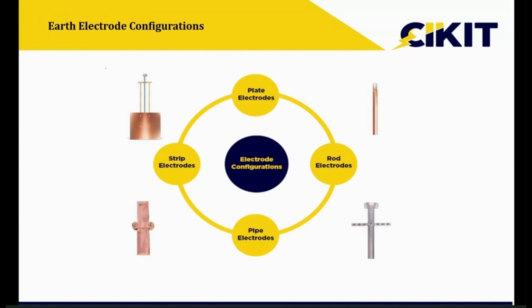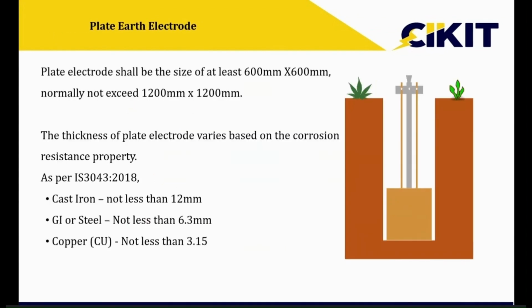The standard has highlighted four different types of earth electrodes: plate, rod, pipe, and strips. If you take the plate earth electrode, generally we use 600 by 600, and depending upon the material, the thickness will be different. The reason for different thickness is to compensate for the effect of corrosion. The corrosion rate is much lower for copper. That is the reason we use only 3 mm thick plates. Whereas if I go for GI or steel, the thickness has to be 6.3 mm, and if it is cast iron, the thickness has to be 12 mm. So the thickness is more not for reducing the resistance value, but for compensating the effect of corrosion, to provide the same lifetime.